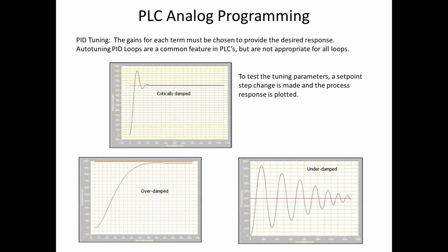And then there's the under-dampened control loop, where the error increases and decreases over time, but it can take a long time to dial in, because it keeps overshooting the set point, but eventually gets it dialed in. It's a process that's probably not desirable. If I had to pick between the control loop tunings, I would prefer one that was critically damped or perhaps over-damped to one that was under-damped. The critically damped gives you control quickly.